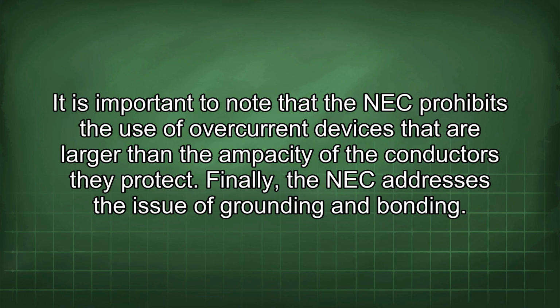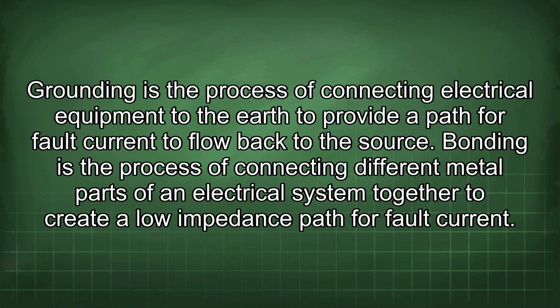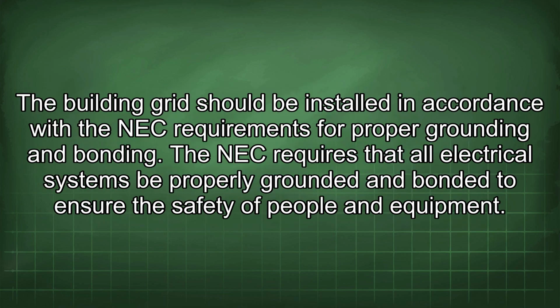Finally, the NEC addresses the issue of grounding and bonding. Grounding is the process of connecting electrical equipment to the earth to provide a path for fault current to flow back to the source. Bonding is the process of connecting different metal parts of an electrical system together to create a low-impedance path for fault current. The building grid should be installed in accordance with the NEC requirements for proper grounding and bonding. The NEC requires that all electrical systems be properly grounded and bonded to ensure the safety of people and equipment.